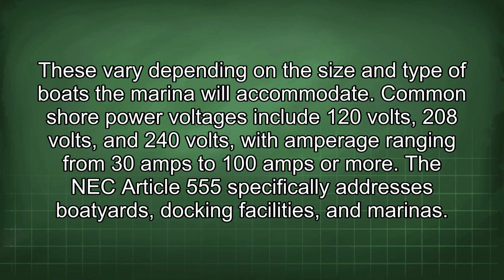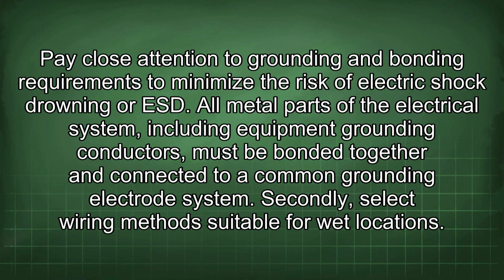Common shore power voltages include 120 volts, 208 volts, and 240 volts, with amperage ranging from 30 amps to 100 amps or more. The NEC Article 555 specifically addresses boatyards, docking facilities, and marinas. Pay close attention to grounding and bonding requirements to minimize the risk of electric shock drowning, or ESD. All metal parts of the electrical system, including equipment grounding conductors, must be bonded together and connected to a common grounding electrode system.